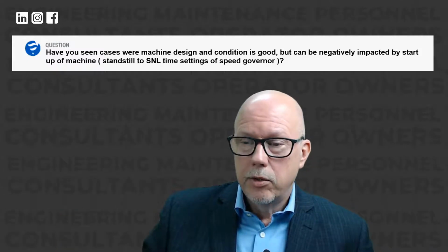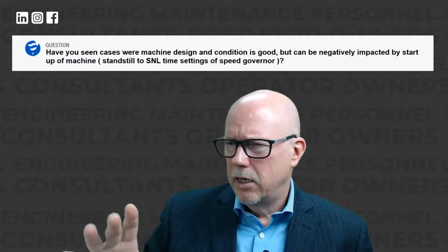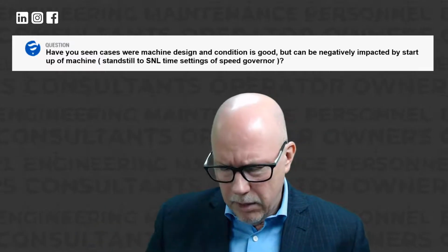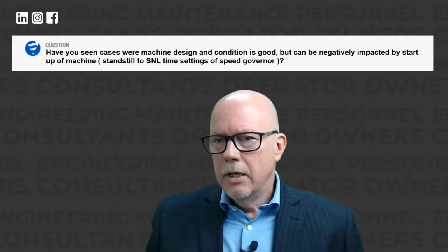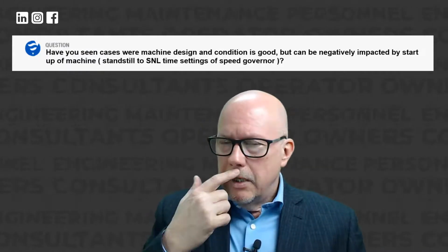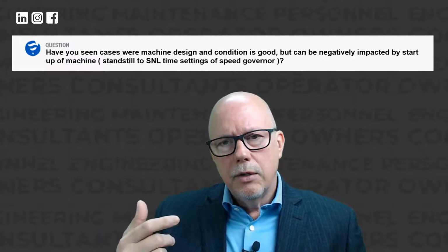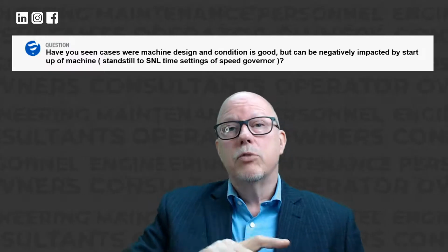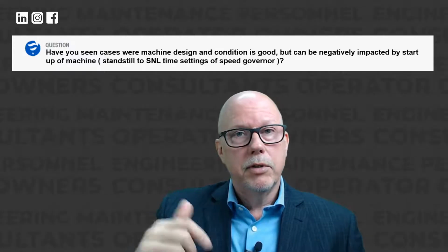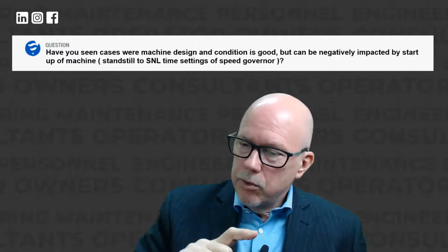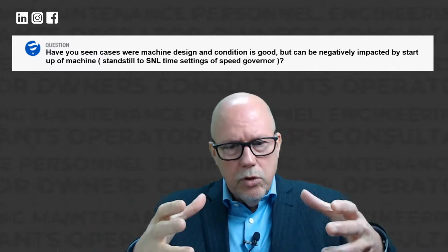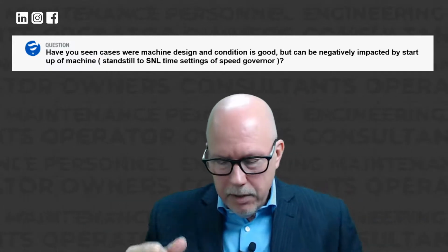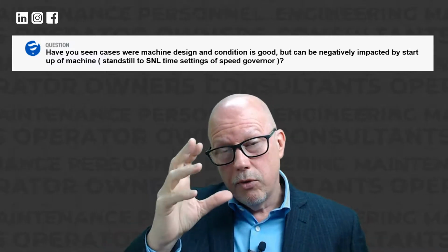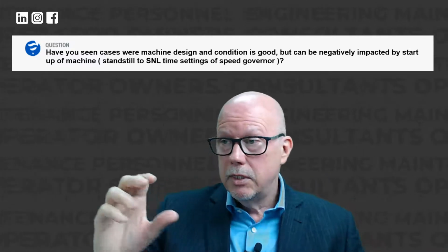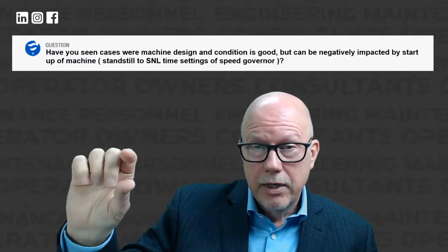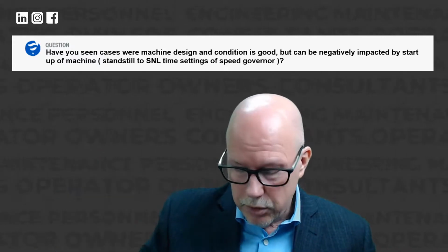They brought the unit speed to 150%, which was about 138 RPM. I talk about this case in our training courses. As they slowed the unit down, at 138 RPM you could see the rim was floating. The rotor shape varied significantly, but that was normal, that was the design. As we decreased the speed, the air gap increased because the rotor was slowly going back to its original shape, and you could actually see the moment where the rim would go back to a shrink fit, decreasing significantly within a few rotations.